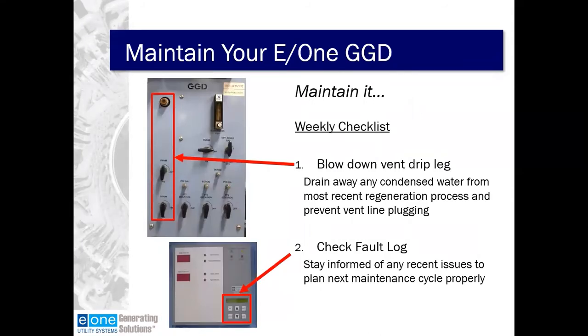So from a maintenance standpoint, we have a weekly checklist and we have an annual checklist associated with the gas dryer. The first thing we'll walk through is our weekly checklist. The first activity we'll talk about is blowing down the vent drip leg. We talked about the regeneration process of the dryer. What happens is the heaters come on and drive off the moisture that's in the molecular sieve. We sweep that moisture up through the vent and out through the planned vent.